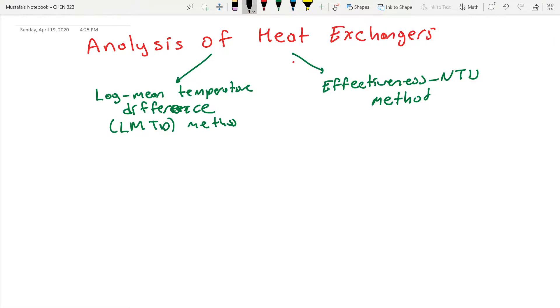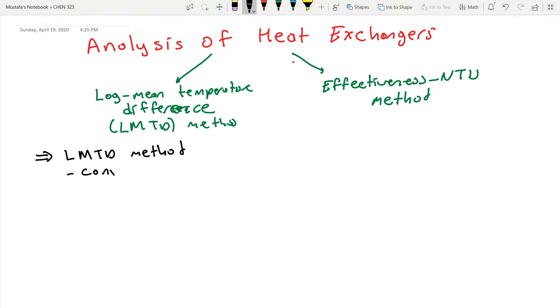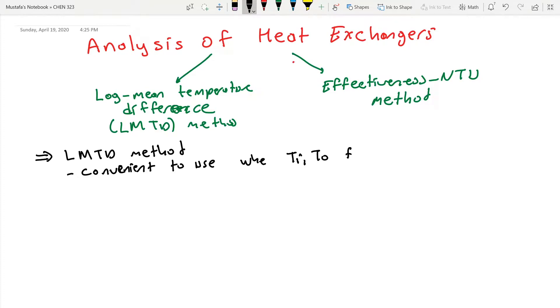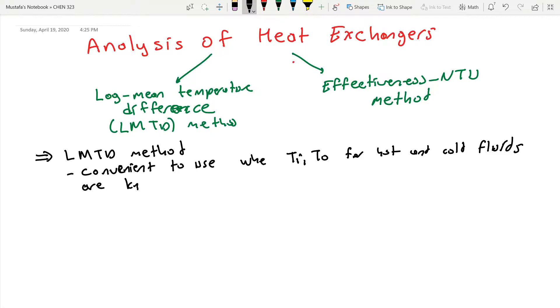Let's see which method is more appropriate for which condition. The LMTD method is convenient to use when T-in and T-out for both hot and cold fluids are known. This is basically a sizing problem.